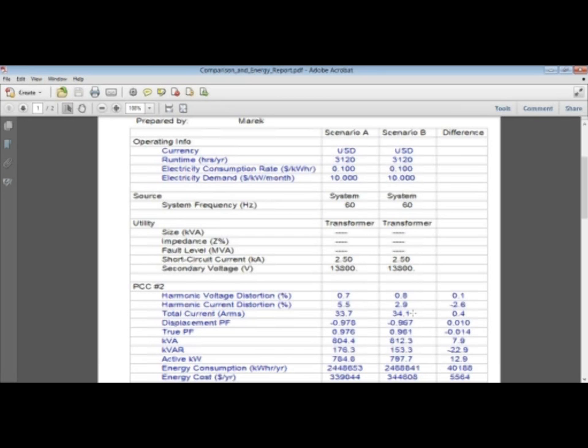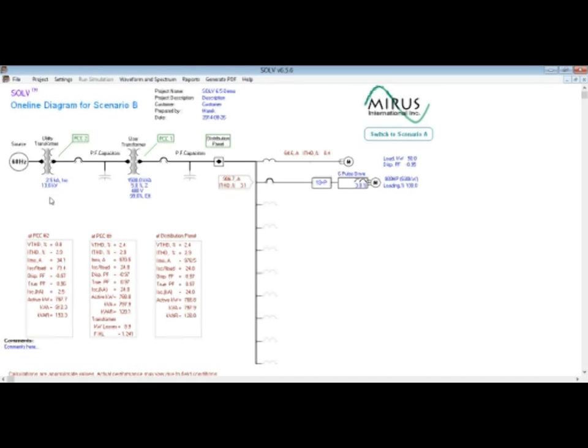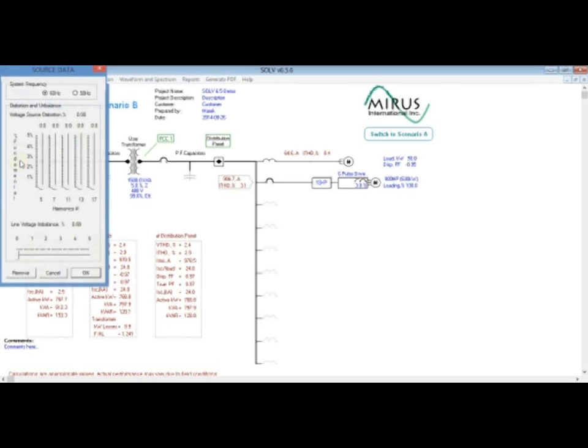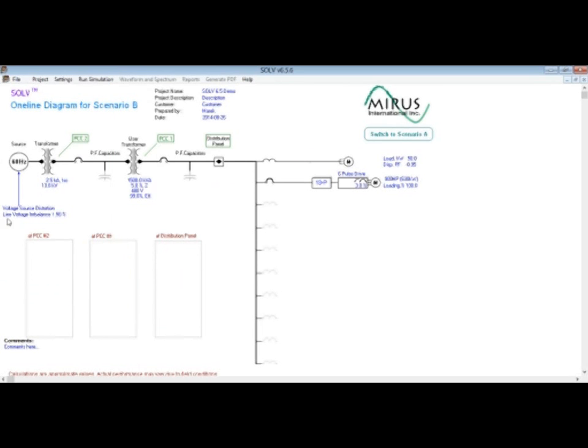We should note that the default conditions are perfectly balanced three-phase voltages with no pre-existing voltage distortion. As this rather seldom exists in real life, we will apply some pre-existing conditions. So I'm closing this report and going to the source, and let's apply about 1.5% voltage imbalance. In many industrial systems, it is very common to measure between 1.5 and 3% of phase imbalance. So I move the slider to about 1.5% and click OK, and you notice that the voltage source distortion and line imbalance shows 1.5% on the single line.